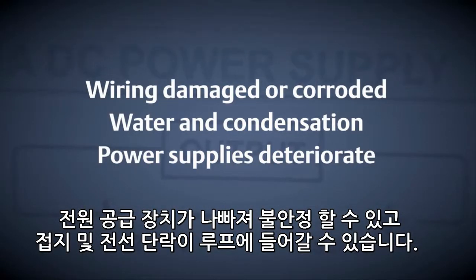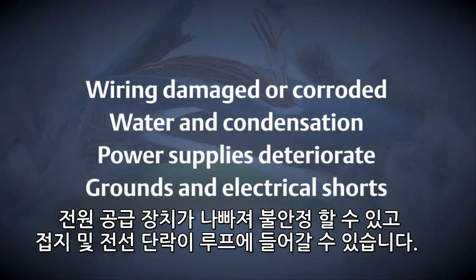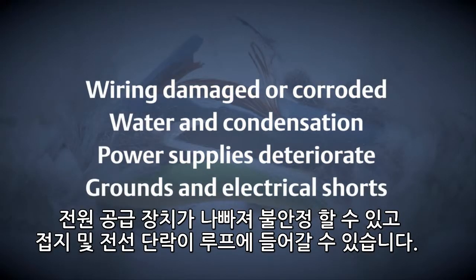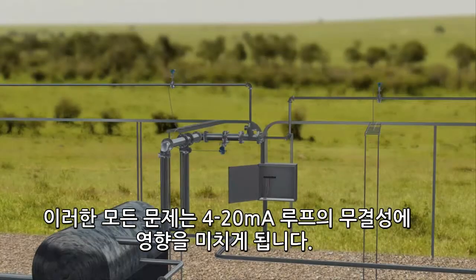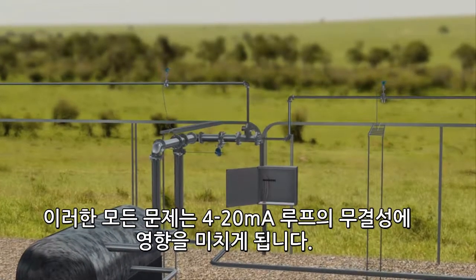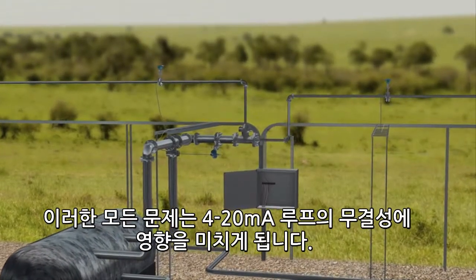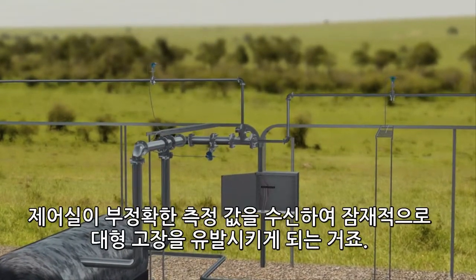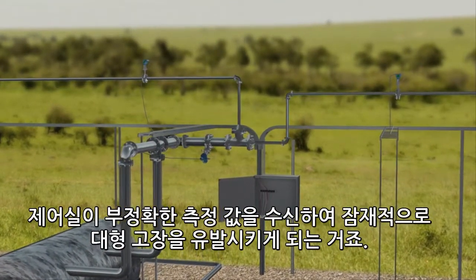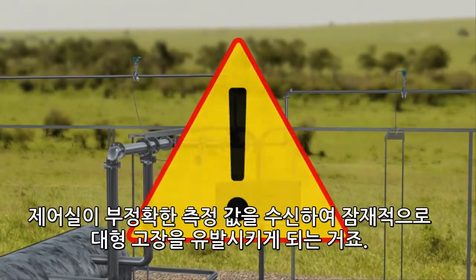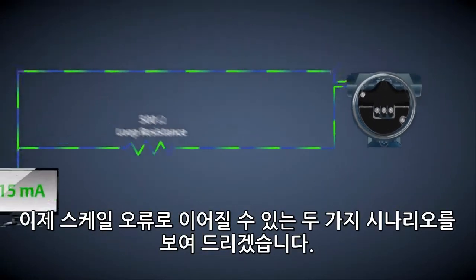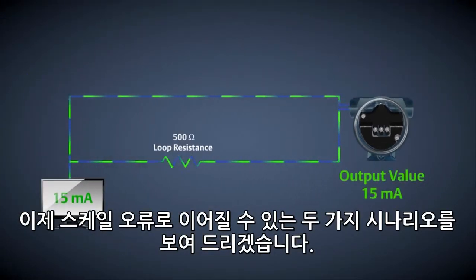Power supplies can deteriorate and become unstable. Grounds and electrical shorts can inadvertently be introduced to the loop. All of these issues can impact the integrity of your 4 to 20 milliamp loop, causing the control room to receive inaccurate measurements and potentially lead to dangerous on-scale failures. Let's picture two scenarios which can lead to on-scale failures.